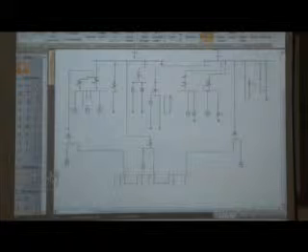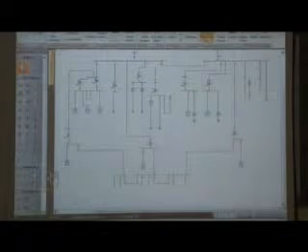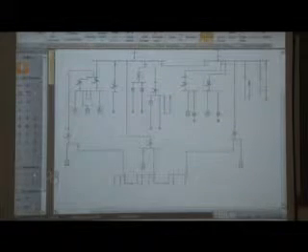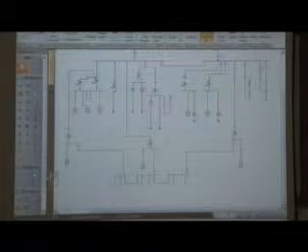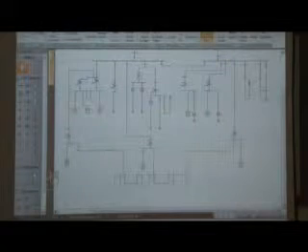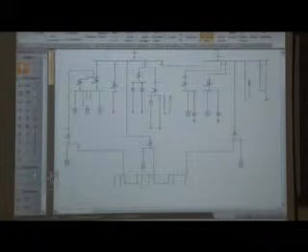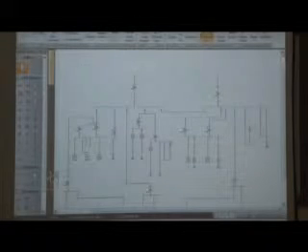And you get down at the bottom, and the old engineer told you, no, these three bottom buses are critical. And you'll notice they're tied together, so if we lose power in one, we have a second source, because we have to keep those things running. And they're fed by two or three transformers. So you look at it and say, well, that looks like a reasonable system, and it's working. Now they have some problems, but it looks fairly decent. So you're satisfied that you've got a single line that seems to work.